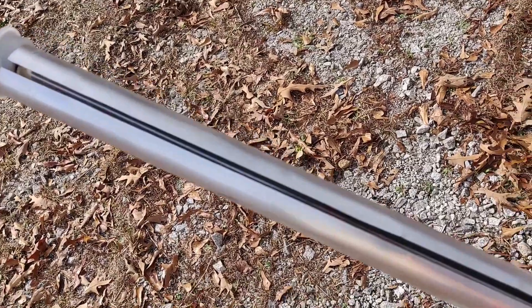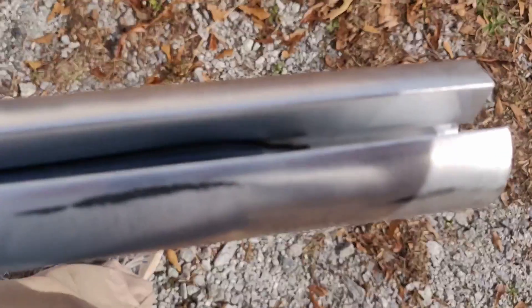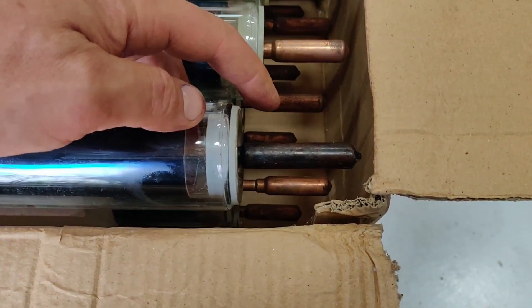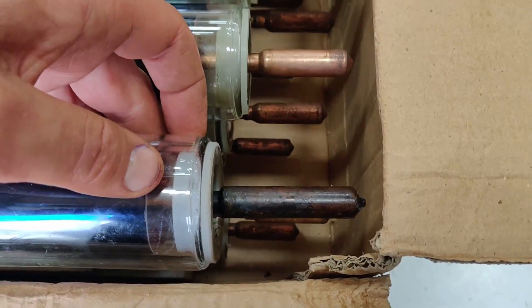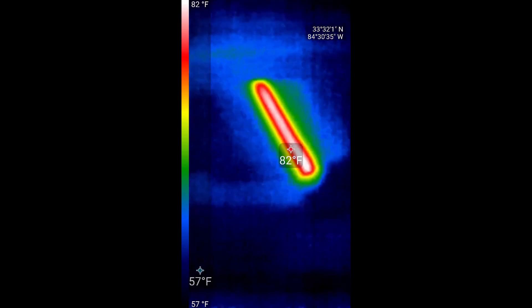This is the heat pipe that's inside of it — it's got aluminum fins just bent into shape that fit around it, and the heat pipe tube goes all the way down to the bottom. There's the bulb at the bottom of it. These are two different manufacturers — these collectors are the exact same diameter but the length of the heat pipe bulb is a little bit longer on the older one, so they come in different lengths. That's the hot outlet of the collectors.